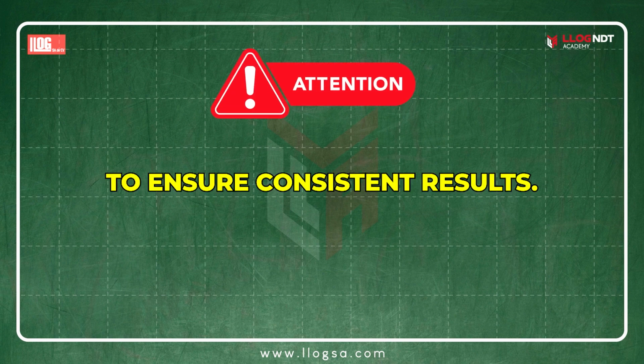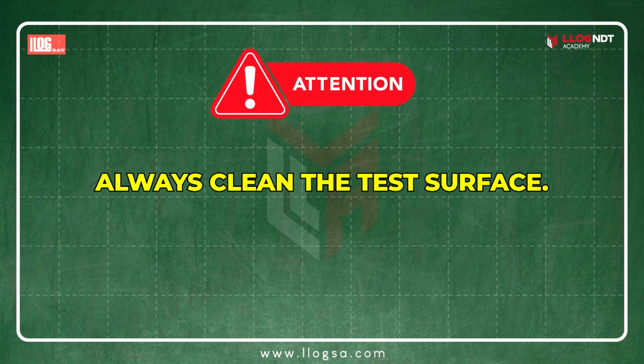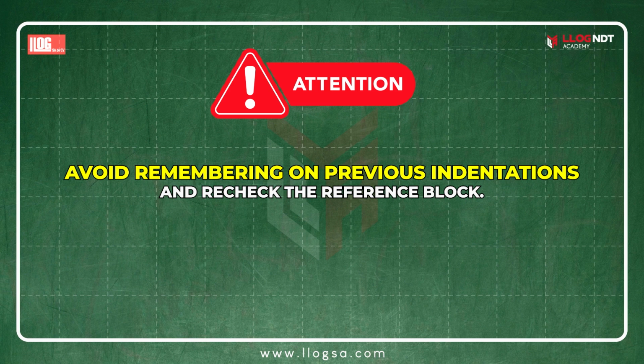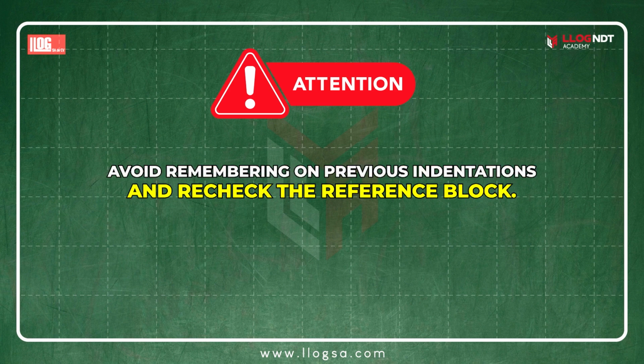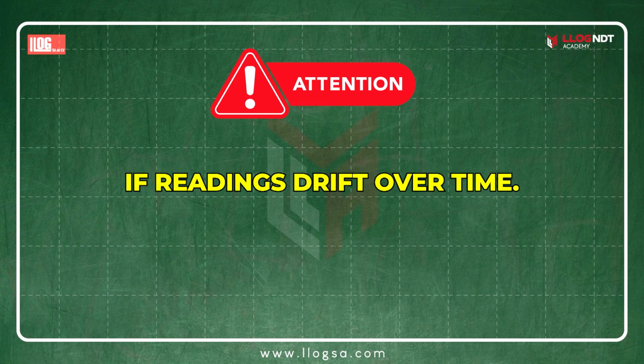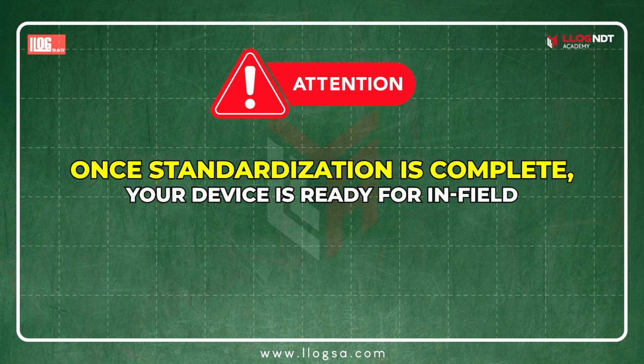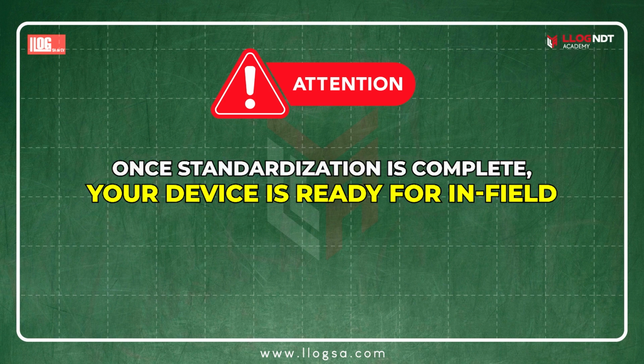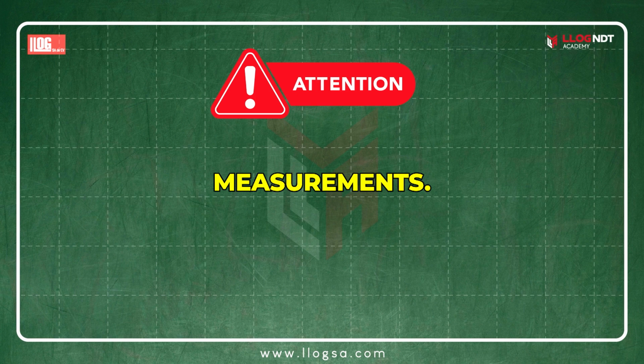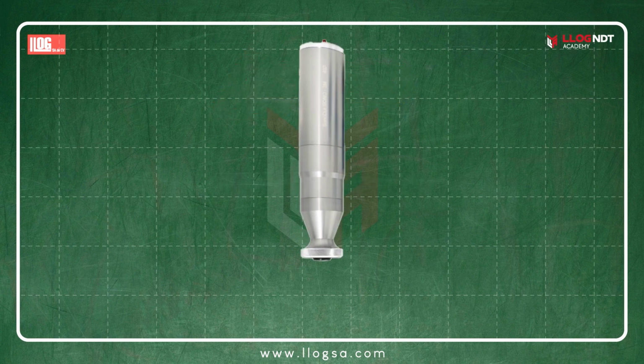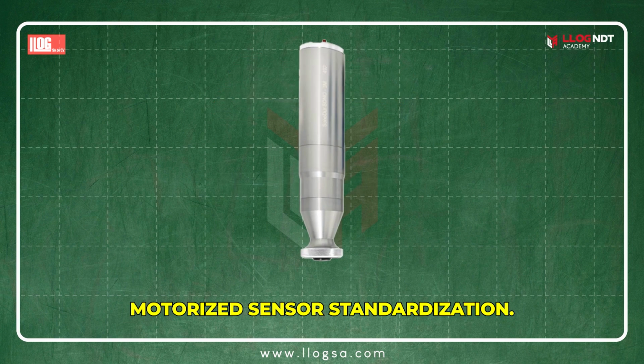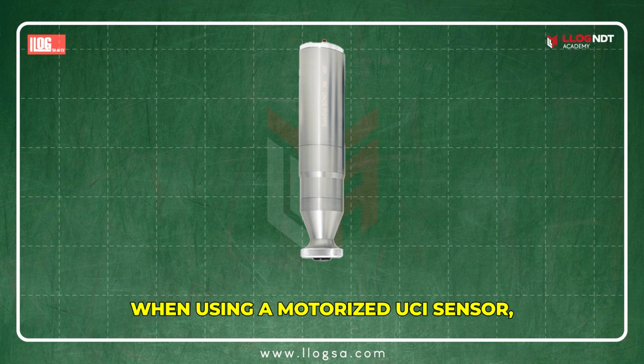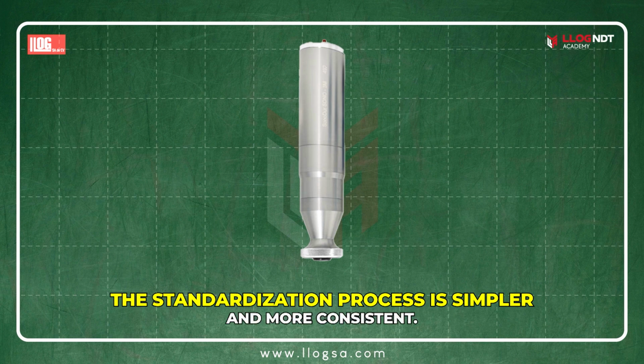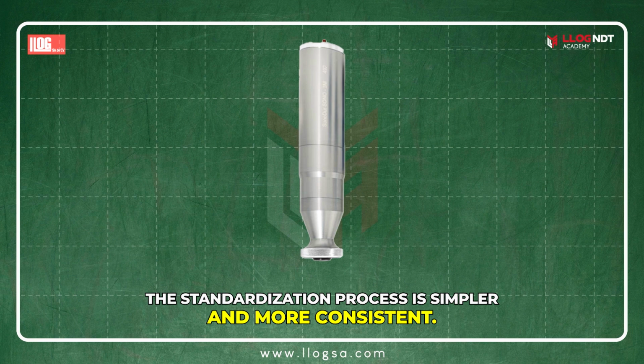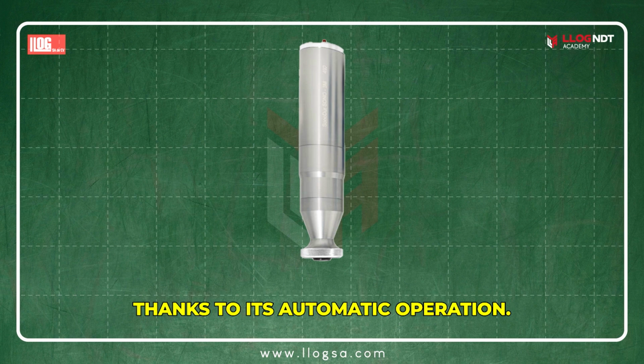To ensure consistent results, always clean the test surface. Avoid remeasuring on previous indentations, and recheck the reference block if readings drift over time. Once standardization is complete, your device is ready for in-field measurements. Motorized sensor standardization. When using a motorized UCI sensor, the standardization process is simpler and more consistent thanks to its automatic operation.